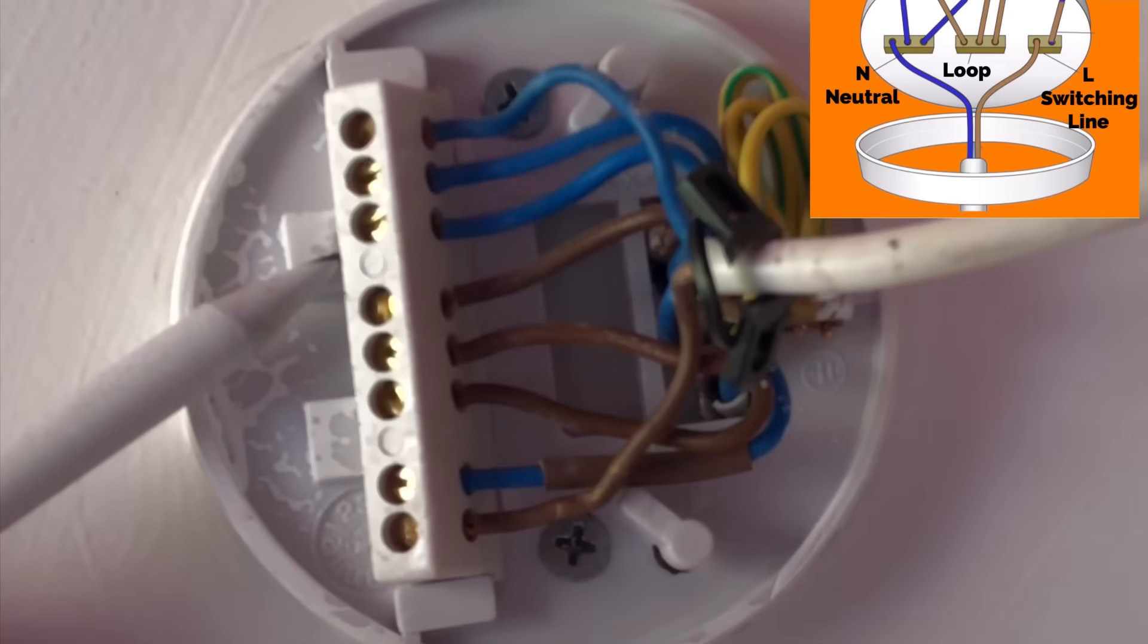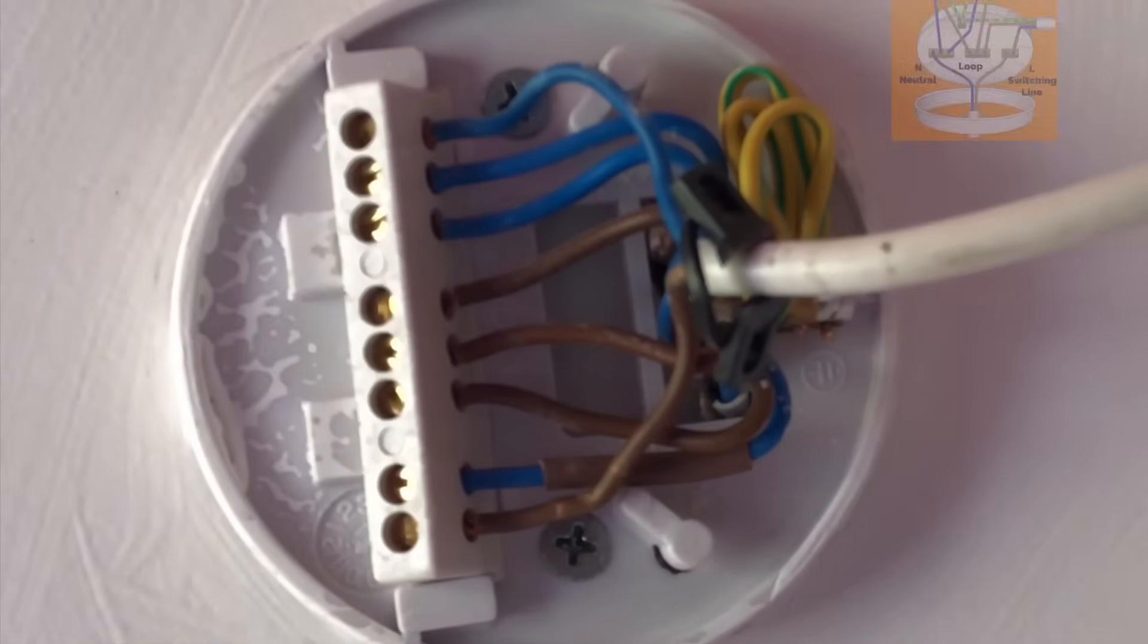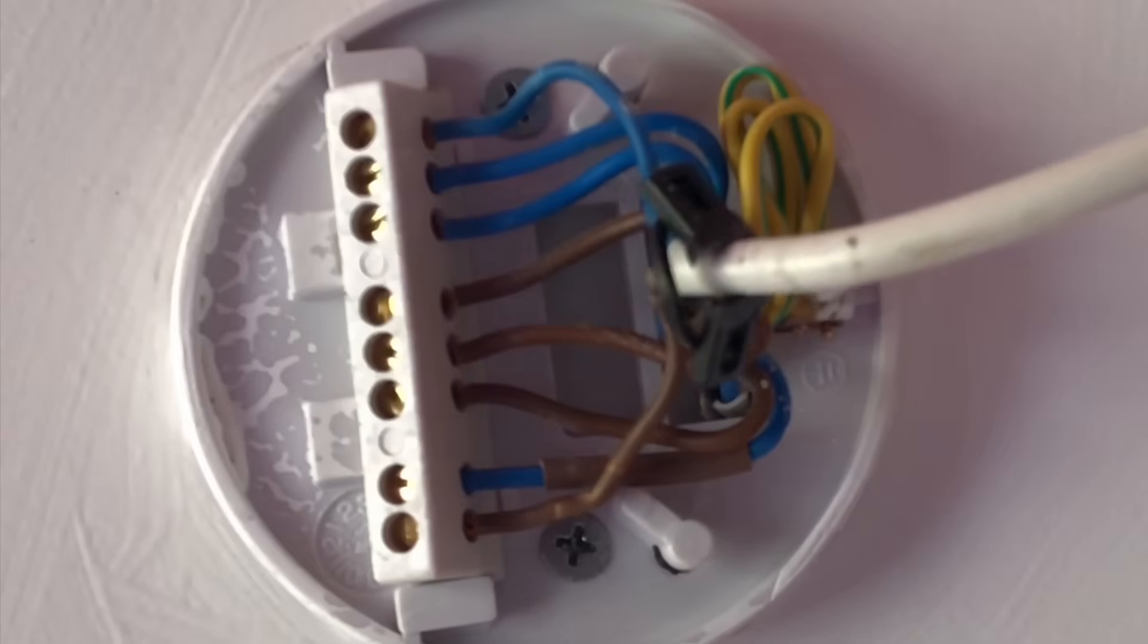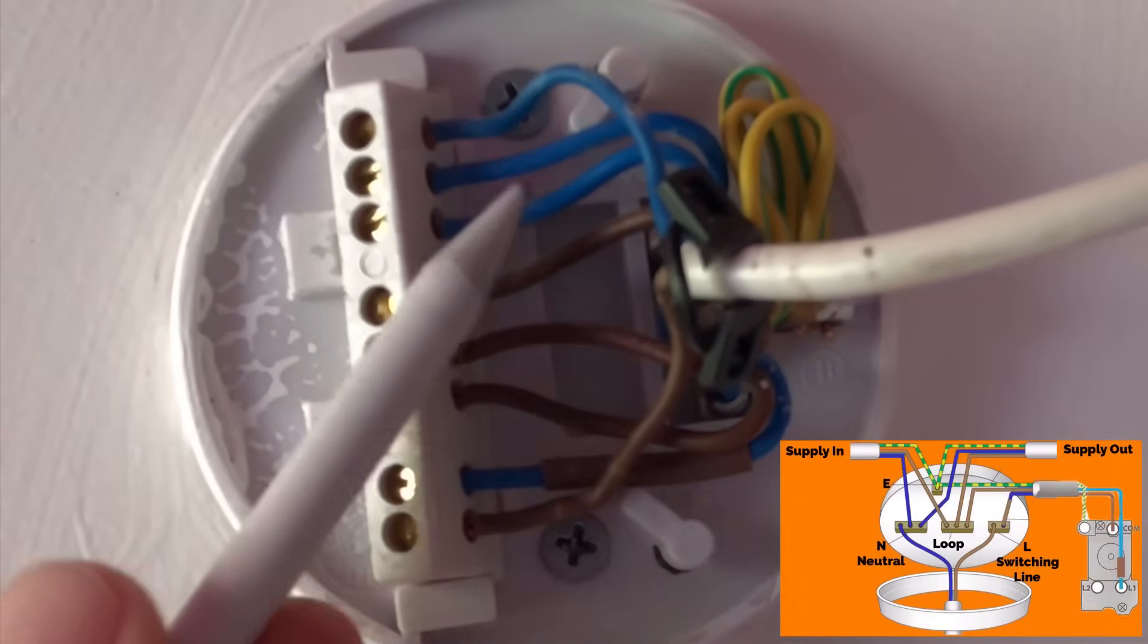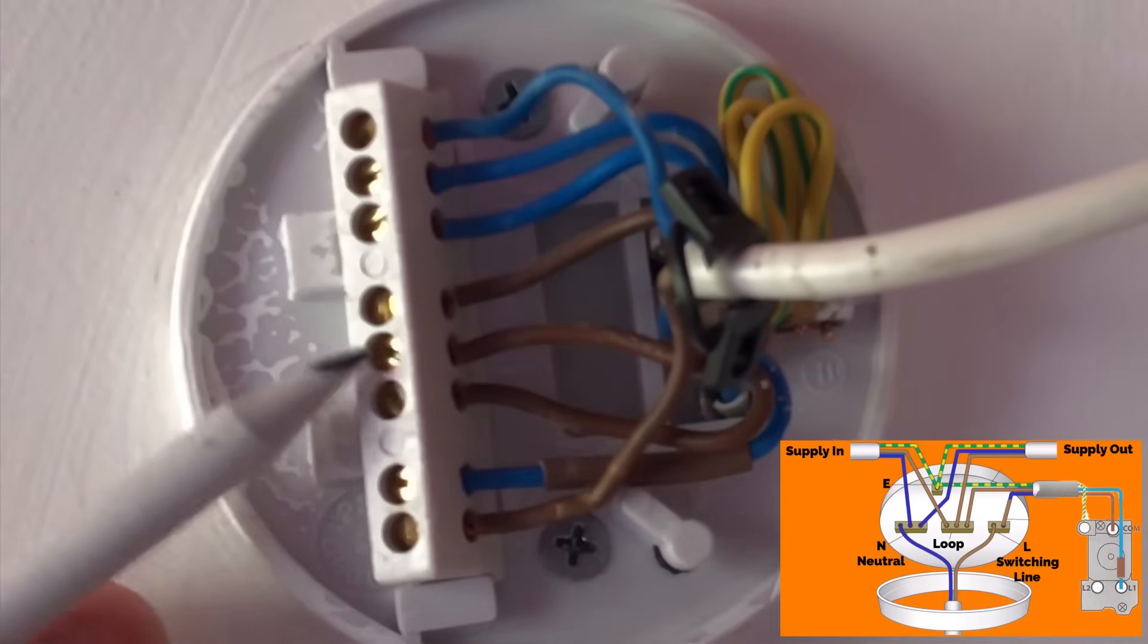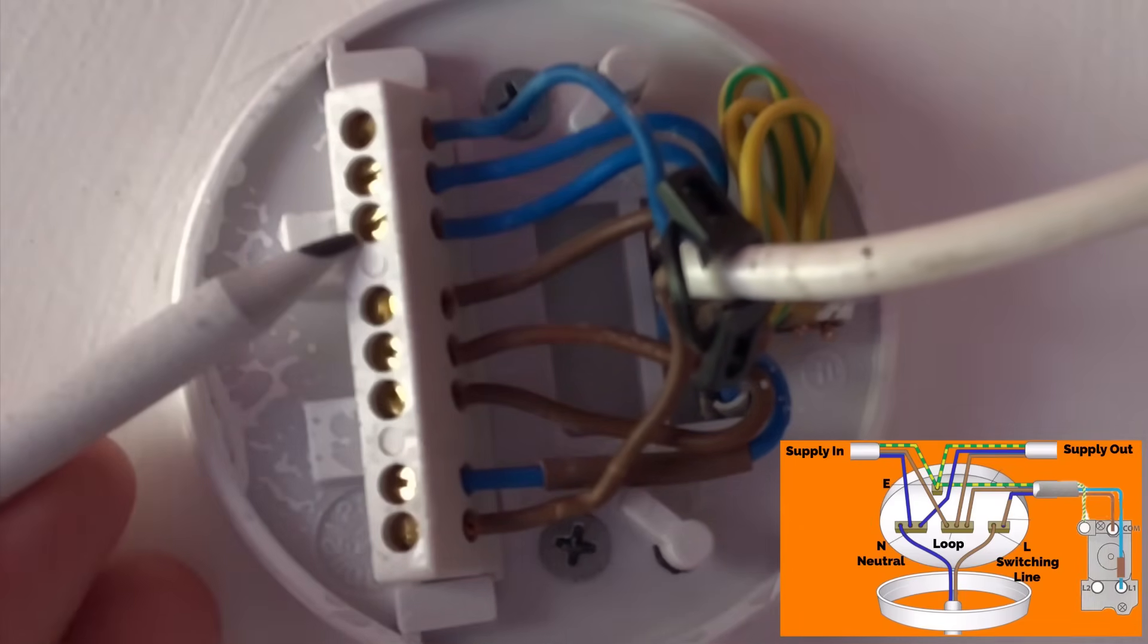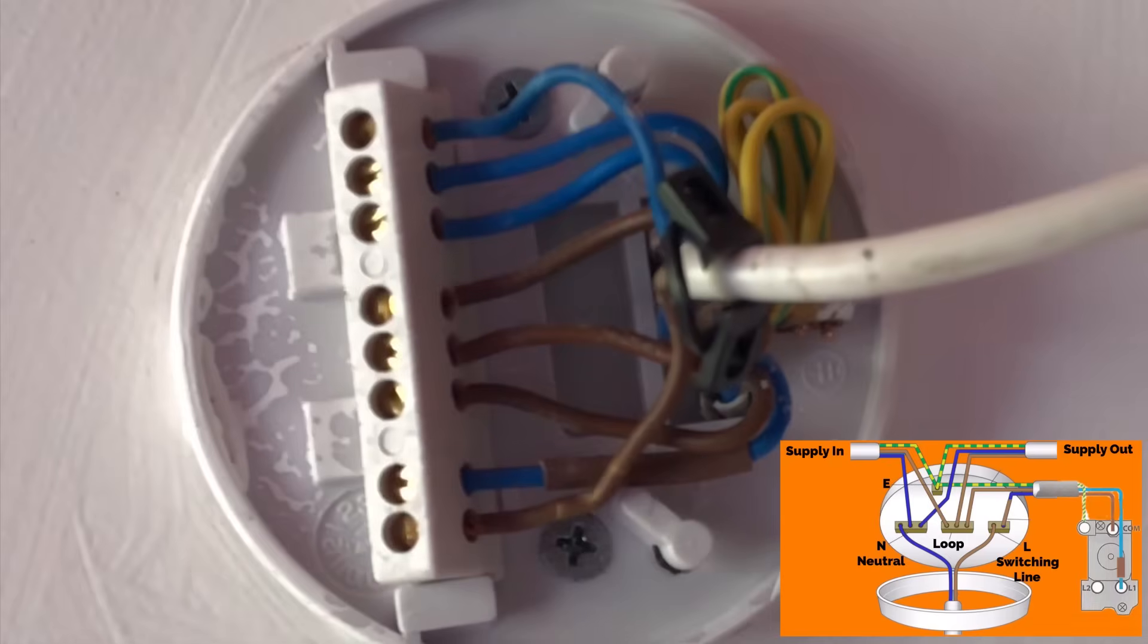So we've got three twin and CPC cables. We've got the supply coming in, so let's say this one here, this brown conductor here and this blue neutral here, would bring a permanent line in and the neutral connection into this ceiling rose. The permanent line is connected in the loop section here and the neutral in this block of three classed as neutral.